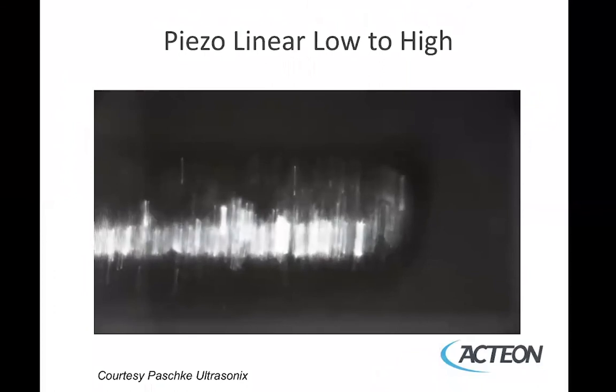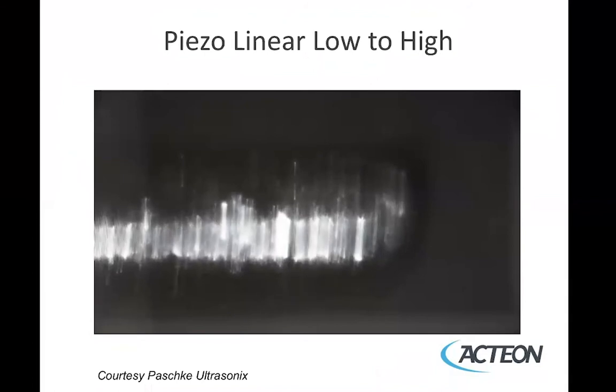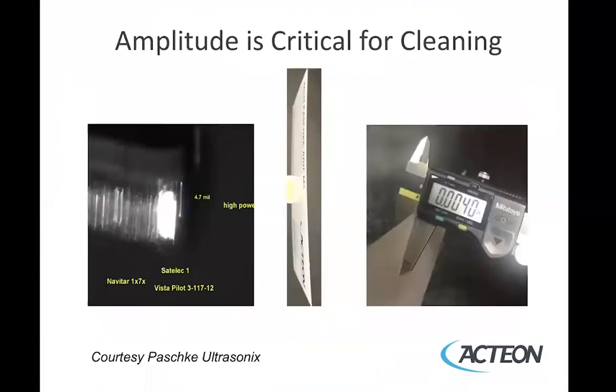This is an example of what the linear stroke looks like under a video microscope. As power goes from low to high, you can see the stroke length becoming longer. The stroke length at high power is about the same as the thickness of a business card — and that's regardless of technology; it's the same for magnetostrictive as well as piezo. This means our technique needs to use overlapping strokes to cover every square millimeter of the tooth.